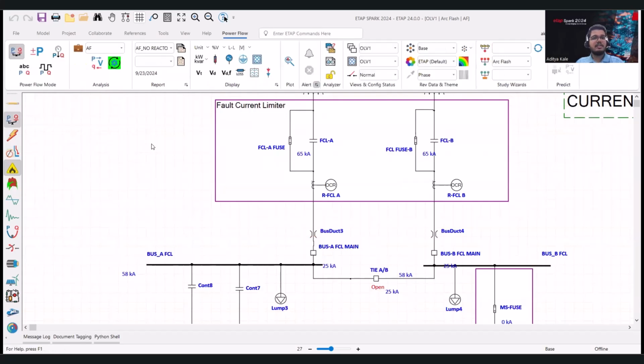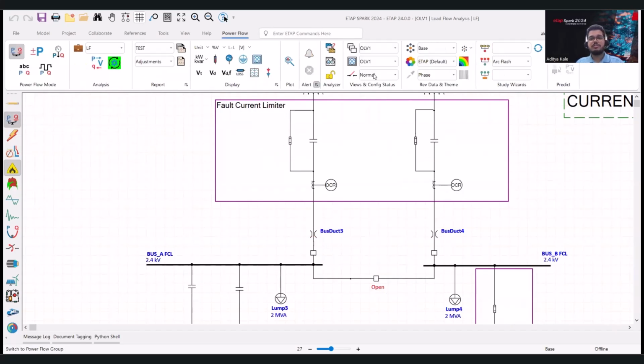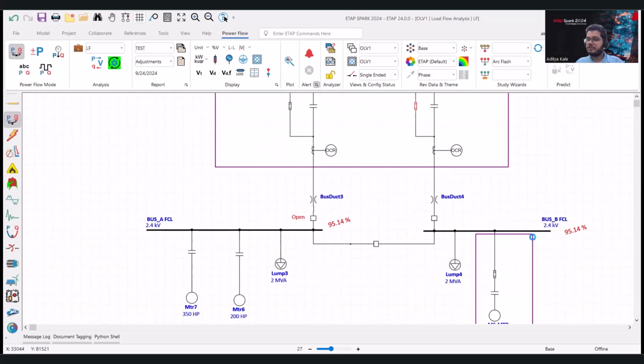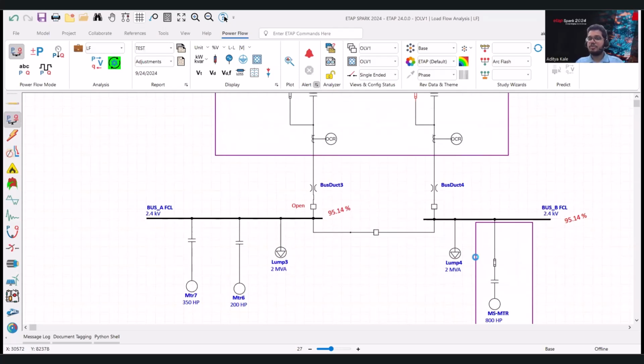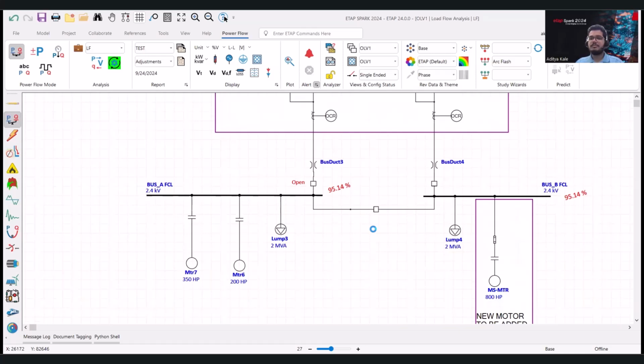And we can take a quick look at the load flow study for the worst case scenario, which is the single-ended. We can see we have a healthy starting voltage of 95%. The motor can be safely started. So even if you have a 15% voltage drop during acceleration, the contactor should be good, and we would not have any nuisance tripping during acceleration. So we can have a very successful motor start as well. That's the end of the ETAP demonstration. Let's summarize our study findings and conclude the presentation.